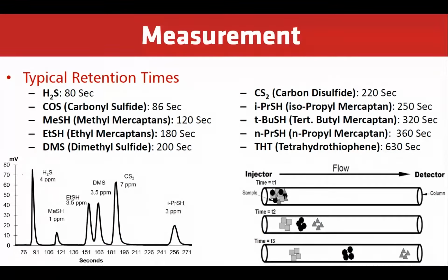Measurement. So the typical retention times, H2S comes out at 80 seconds, COS or carbonyl sulfide at 86 seconds, methylmercaptan at about 120, ethyl mercaptan at 180 seconds, and dimethyl sulfide at approximately 200 seconds. So you can see the chromatogram as the sulfurs are separated through the GC section of the oven. The individual peaks will come out in this typical order.